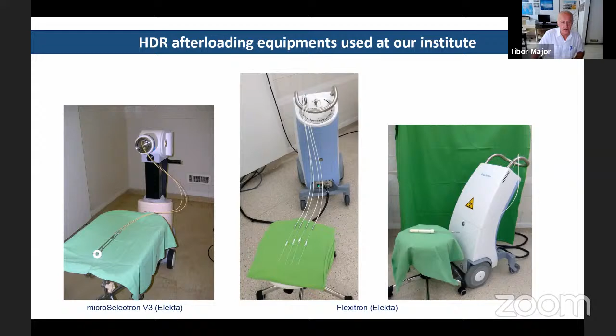This slide shows the main parts of an HDR afterloading equipment. This is the head of the equipment, and there is a source container in the middle, and the radioactive source is positioned in its center. It is important that only one source is in the equipment. There is a stepping motor here, and this motor can drive out the source through this transfer tube to the applicator, which is inside the patient. After that, it pulls back to the container. So this is how an afterloading equipment works.